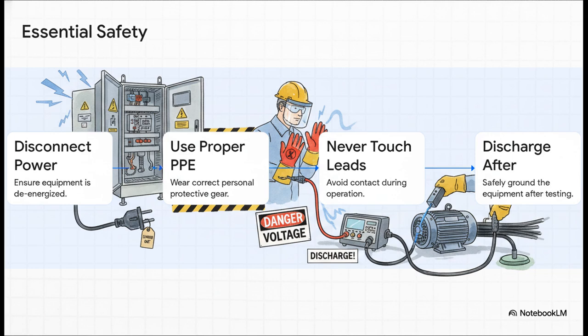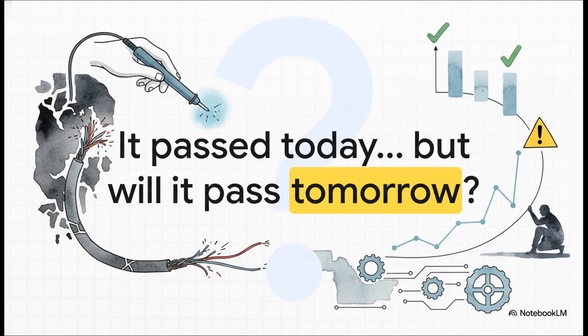First, always make sure the equipment is completely disconnected from its power source, de-energized. Second, wear your PPE. Third, never ever touch the test leads while the Megger is running. And finally, and this is the one people sometimes forget, you have to discharge the equipment after the test. Cables and windings can hold a charge like a capacitor, and you need to safely ground that charge before you touch anything.